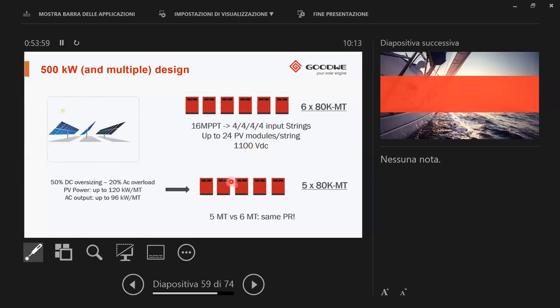But I want to put also to your attention the possibility to decrease the number of MT inverters by one. So instead of using six, you can also use five inverters, which of course are big savings from an economical point of view. And this configuration, as I said, is supported by the capability of our MT series to have 50% DC oversizing and 20% AC overload, which means this configuration, from a planning point of view, is workable to the realization of a 500 kilowatt solution. According to our experience and according to the PVSYST simulation, you have the same performance ratio by using these two configurations. With six or with five, you get the same performance ratio.